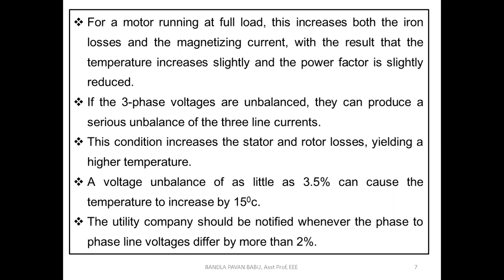Next, the utility company should be notified whenever the phase-to-phase line voltages differ by more than 2%. Suppose they have given a 3.5% voltage unbalance; then a 15 degree temperature rise occurs. Based upon this, they fix that between two phases, if the unbalance exceeds 2%, they analyze it with the help of power quality analyzers and other measuring equipment. If the difference between the two phases exceeds 2%, obviously they need to take preventive action.